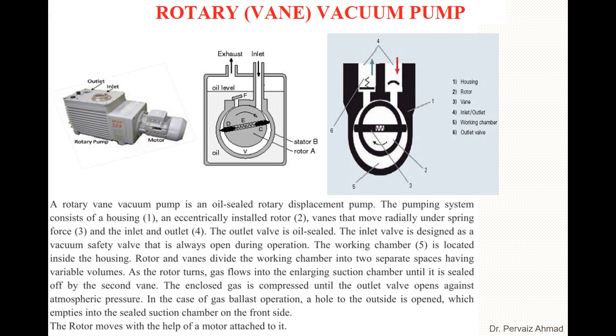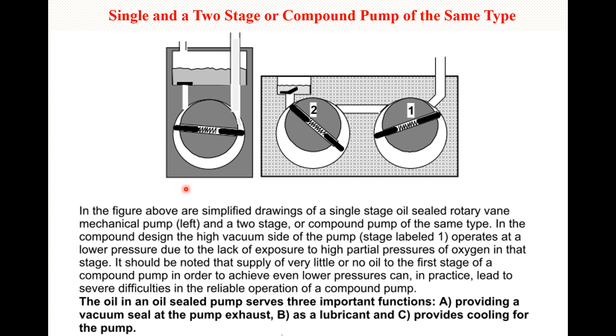Rotary vane pumps come in two types: single stage and double stage. The double stage is also called a compound pump and is designed for higher vacuum. Unlike the single stage, where we have a simple rotary vane oil-sealed mechanical pump, the compound pump is designed in two stages.